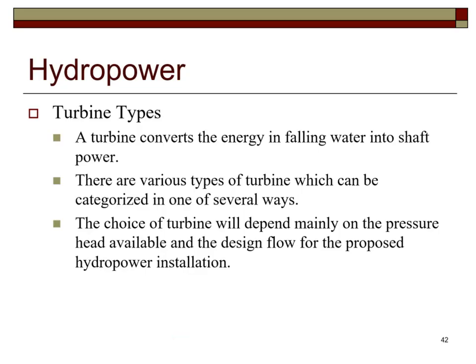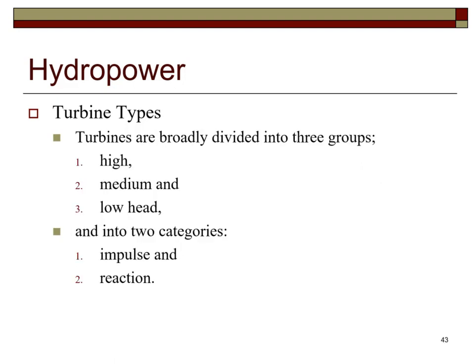A turbine converts the energy in falling water into shaft power. There are various types of turbines, and the choice depends mainly on the pressure head available and the design flow for the proposed hydropower installation. Turbines are broadly divided into three groups—high, medium, and low head—and into two categories: impulse and reaction.